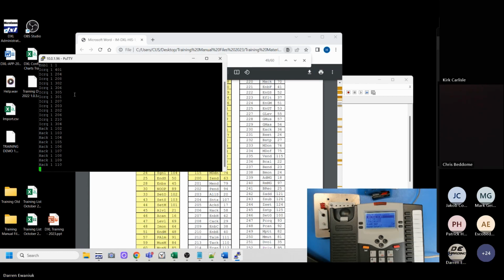Okay. So this is a very good way of checking your software to make sure your software can handle all the activity coming in, that you're not missing something. I believe the same thing goes for the PLC. If you're peer-to-peer and you send a single stat request, it'll update everything that is peer-to-peer to that PLC. Is that correct? Yes, whether it's peer-to-peer or polled, it's the same thing. It will send all the responses as if they happen right now.